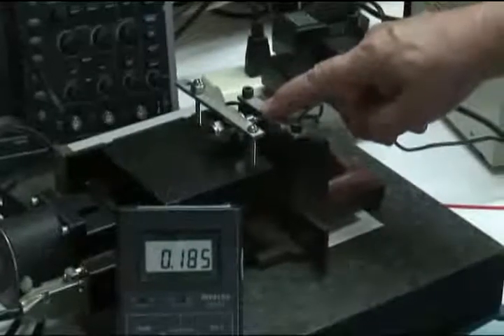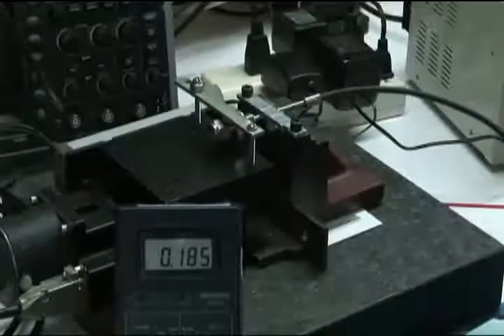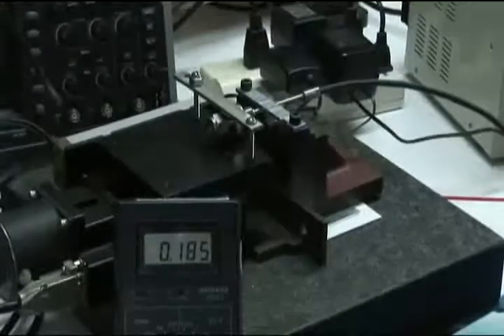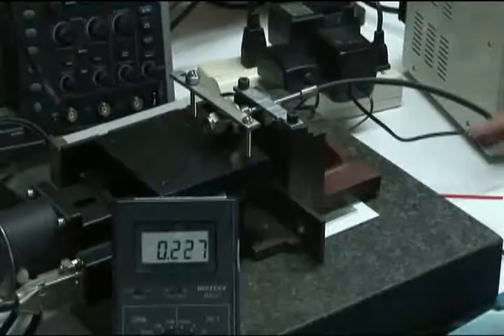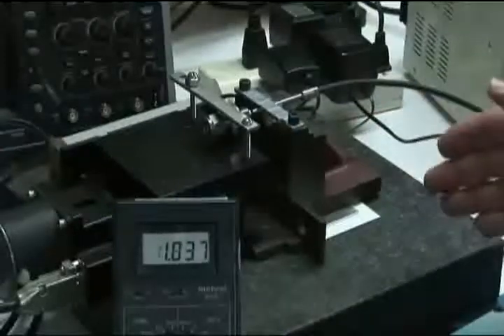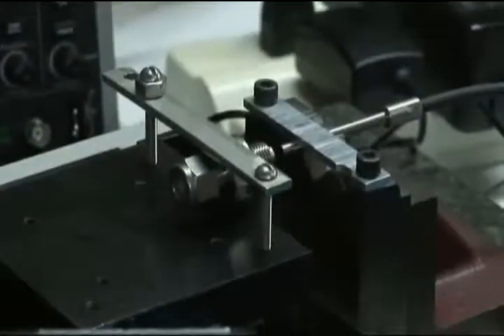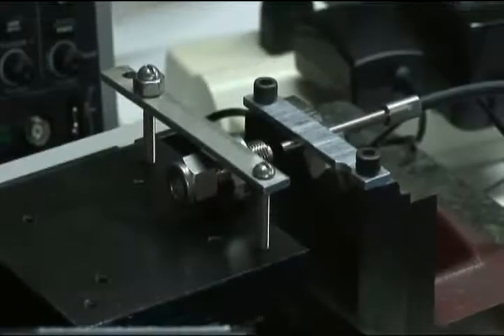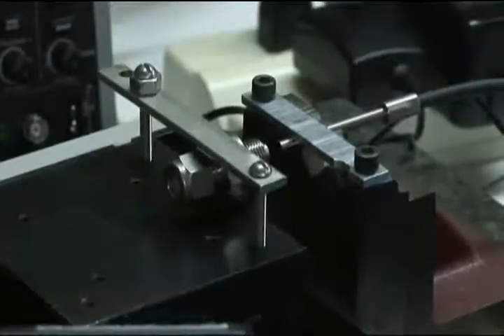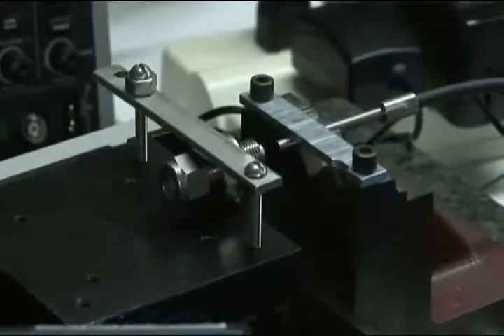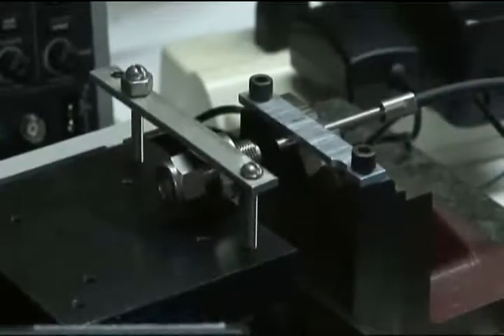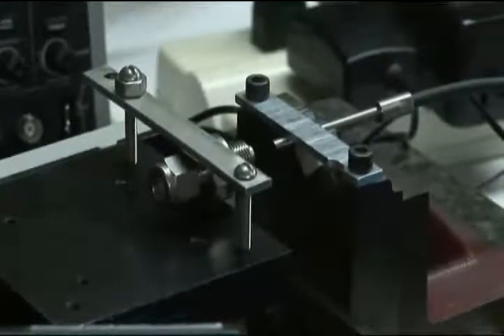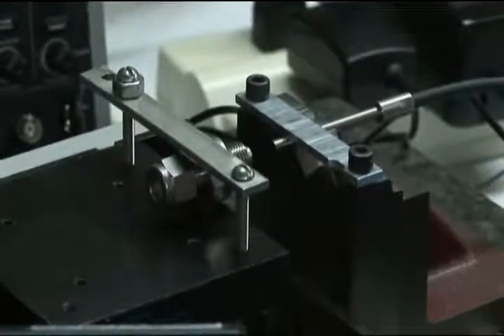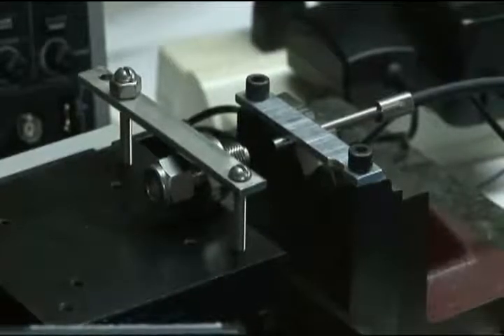Okay, so now we have the stage set up. We're in contact with the probe, and we're going to tell the computer to start running this calibration. So now you can see the stage is moving in steps. Each time the stage stops, we have a linear encoder on the side here, a 4-microinch encoder. So the PC reads the sensor output and the stage encoder values at each step, and it's loading them into our file. Now when this is done, we'll be at exactly 1/2 inch gap from the sensor.